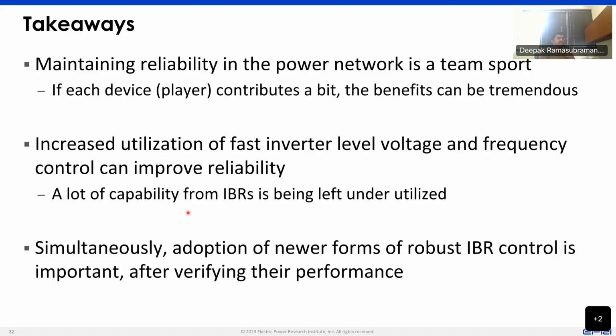Which means that each device, each player in the network, contributes a bit, and because of that, the benefits can be tremendous. In order for them to contribute, there is a lot of capability that is underutilized or not utilized in the network, which is just lying on the table and not being made use of for the network itself. If we find ways to unlock that capability, that can be really beneficial for the network. An example of that is increased utilization of fast inverter-level voltage control and frequency control that can help improve the reliability of the network.